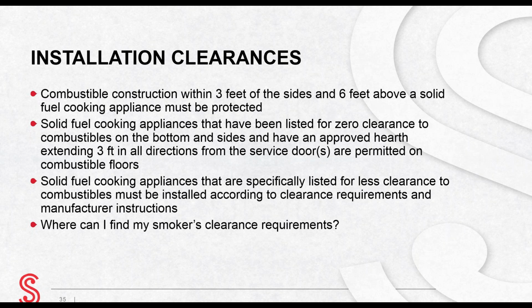Solid fuel cooking appliances that have been listed for zero clearance to combustibles on the bottom and sides and have an approved hearth extending 3 feet in all directions from the service doors are permitted to be used on combustible floors. Solid fuel cooking appliances that are specifically listed for less clearance to combustibles are permitted to be installed in accordance with the requirements of the listing and the manufacturer's instructions. Where can you find the clearance requirements for your smoker? Manufacturers list clearance requirements in the owner's manual and on a metal placard, often in the back of the unit.